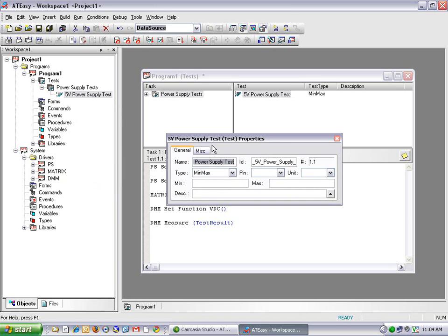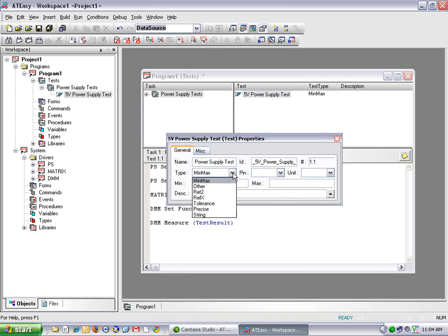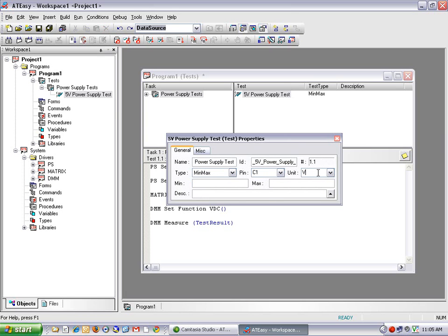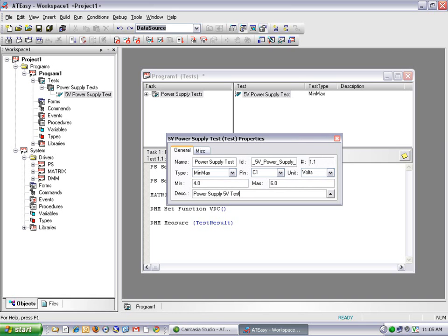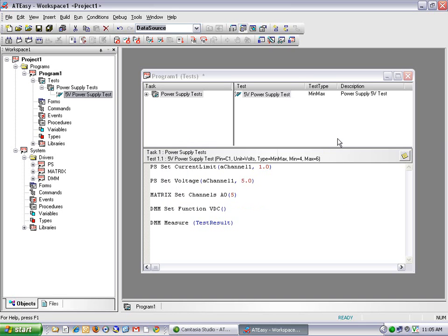So I can right-click on my 5-volt power supply test and select properties. And I can fill in the correct parameters for my test. In this case, I'm going to leave the default choice of min-max for test type. I enter a value for my pin. I enter volts for my units. And select 4 volts minimum and 6 volts maximum. And finally, a description for my test.